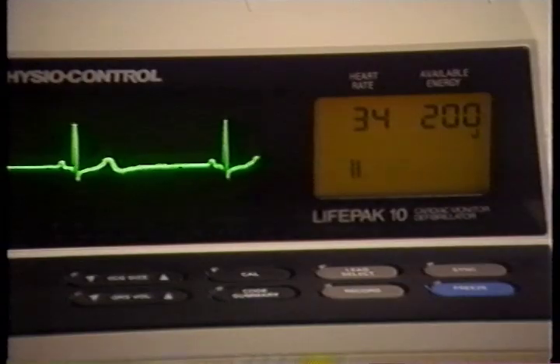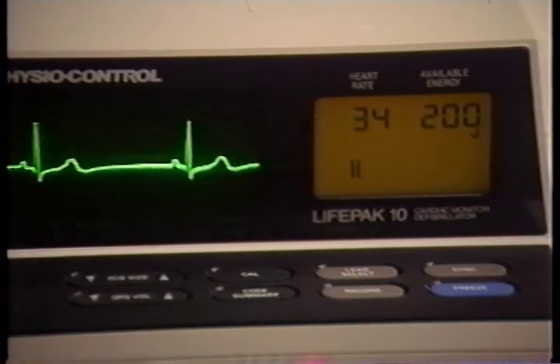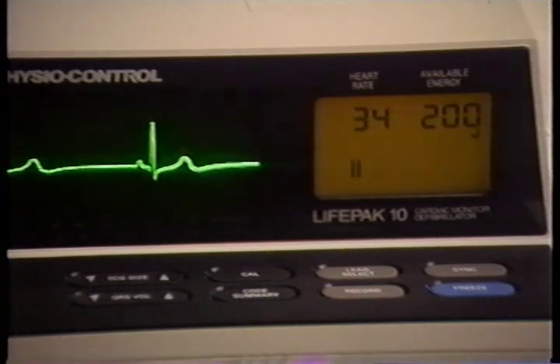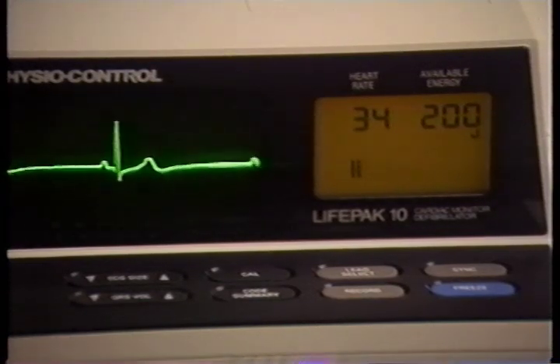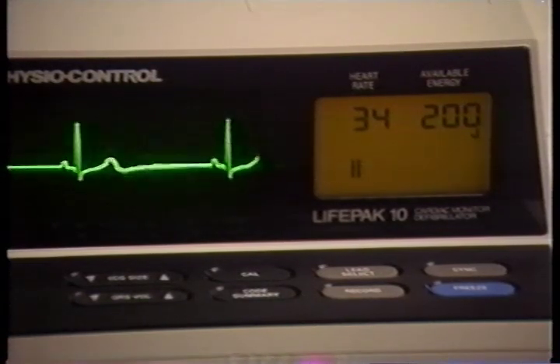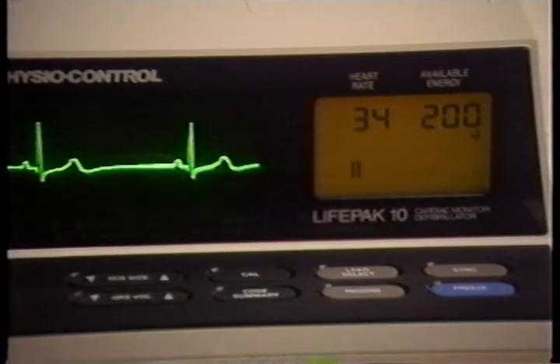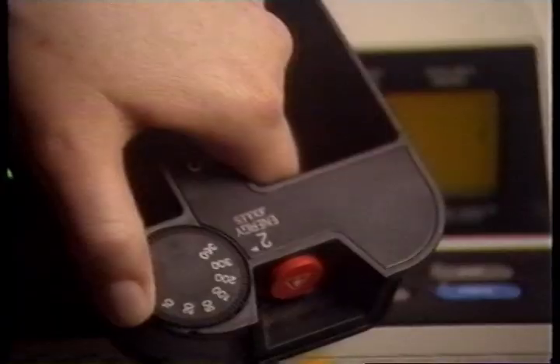When the defibrillator is charged, energy is available for approximately 1 minute, and then the energy will internally dump. If defibrillation is not necessary and you need to internally dump the stored energy before 1 minute, change the energy level on the sternum paddle to disarm the defibrillator.